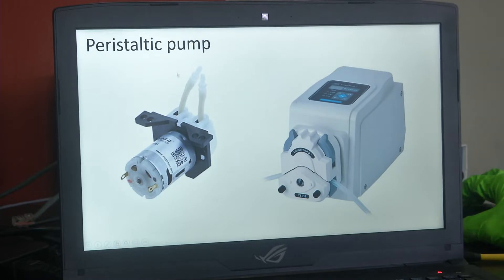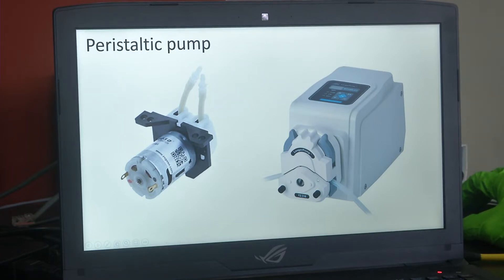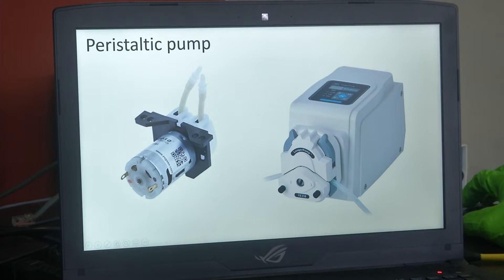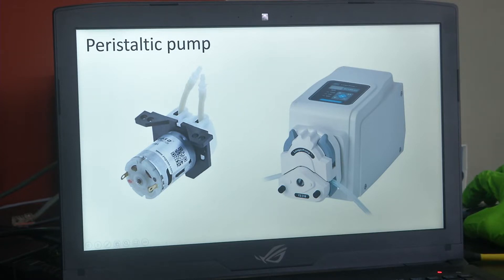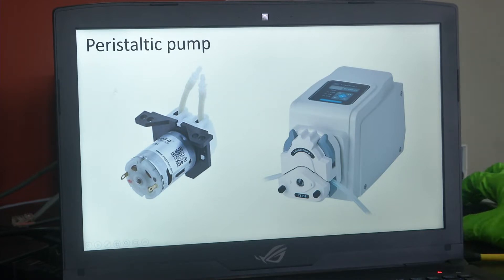On the screen you can see two pumps — this is a 12 volt peristaltic pump, and this is a more expensive peristaltic pump for microfluidic applications, similar to what you may have seen in the lab videos. These peristaltic pumps are positive displacement pumps used for very precise applications, especially in microfluidics, drug delivery, and other areas where flow must be controlled very accurately. The larger peristaltic pump can regulate flow in rates of millilitres per hour and can displace higher volumes as well.